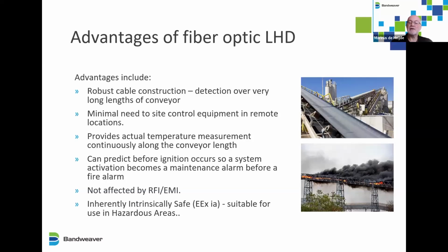This fiber optic linear heat detection is also not affected by radio frequency interference or electromagnetic interference, and it's inherently safe. We have got an EX approval, which makes it suitable for use in hazardous areas.